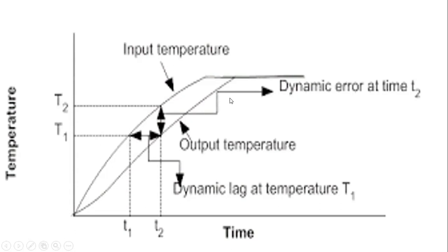The dynamic error is always referenced with respect to a specific time: maximum dynamic error occurs at time T2. Maximum lag is at temperature T1. The lag is always referenced with respect to the output value, whereas the dynamic error is referenced with respect to time. Understanding this helps when designing control systems.